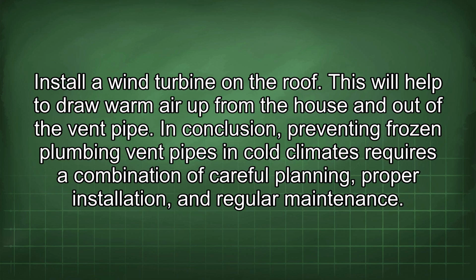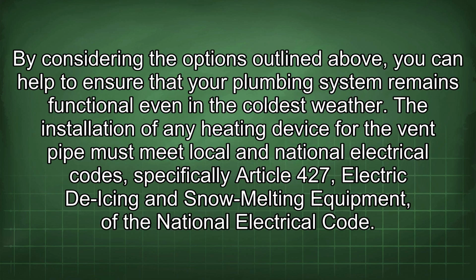In conclusion, preventing frozen plumbing vent pipes in cold climates requires a combination of careful planning, proper installation, and regular maintenance. By considering the options outlined above, you can help to ensure that your plumbing system remains functional even in the coldest weather. The installation of any heating device for the vent pipe must meet local and national electrical codes, specifically Article 427, electric de-icing and snow melting equipment, of the National Electrical Code.